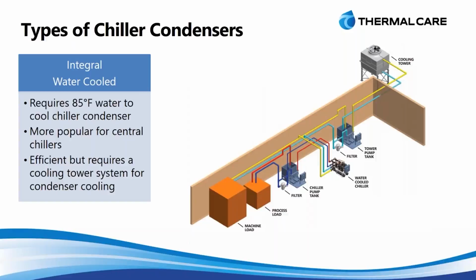But what's unique about a water-cooled chiller now is that it's using a different water source to actually pull the heat out of the chiller that the chiller has removed from the process. We use typically a cooling tower for this, and a cooling tower uses evaporation rather than refrigeration. And so while it can still reject heat, it can only achieve about an 85-degree temperature, whereas a chiller can go much lower. So what this allows us to do is use our chiller, but then also use this higher level of temperature water available to reject the heat.